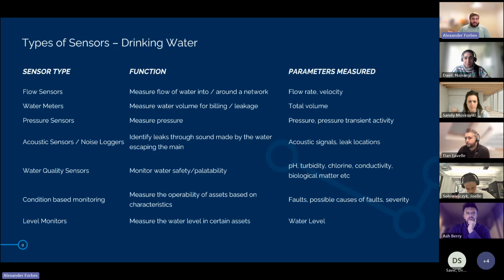As pointed out earlier, you've got your flow sensors and your water meters. We specify that difference because our flow sensors generally provide time series data - this is what the flow is right now, and then we'll take another sampling in a minute, two minutes, five minutes, however long. Your water meters provide a totalized flow, how much of that flow has gone through the meter, so we can do things like leakage calculations, billing, or working out how much water the treatment works has produced over a given period. But ultimately, they're both just measuring how much water is flowing through them.